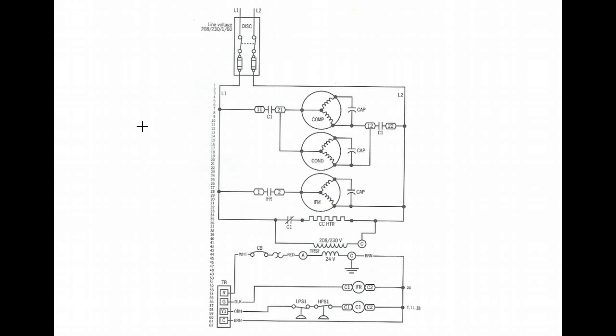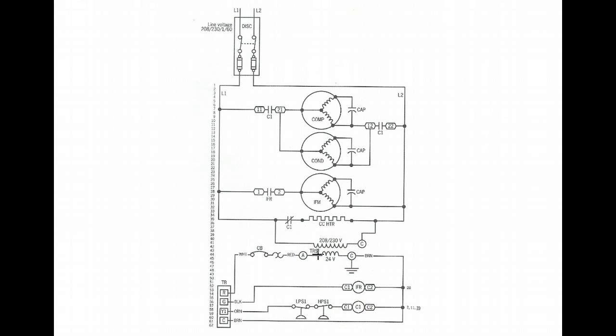When you're looking at a schematic circuit such as this — and this happens to be a straight cool air conditioning system — the circuit has power applied. There's 208/230 volts coming in, 24 volts at the transformer, and the system is at rest. There is no call for cooling. There is 24 volts on the R terminal going out to the thermostat, but the thermostat is not calling for anything at this time.